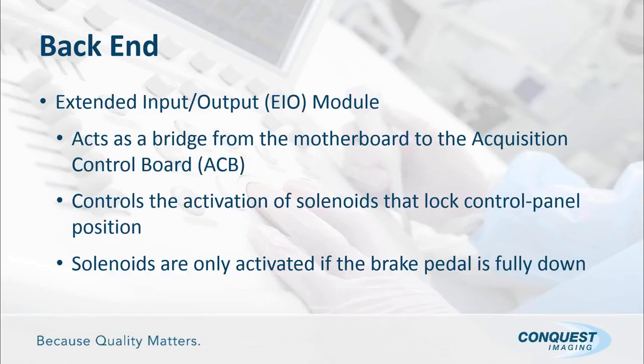Moving on, we have the extended input-output module, and I mentioned that the acquisition control board is the interface between the front end and back end, and it does that through the extended input-output module. So it acts as a bridge between the front end and back end. It controls the activation of solenoids that lock the control panel. This is an interesting feature on the Epiq. In order to move the control panel up and down, left and right, I'd have to activate the solenoids.